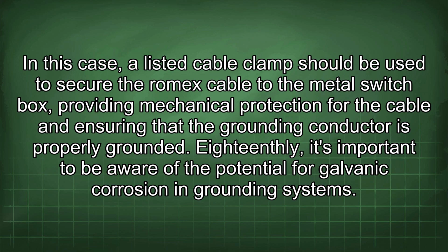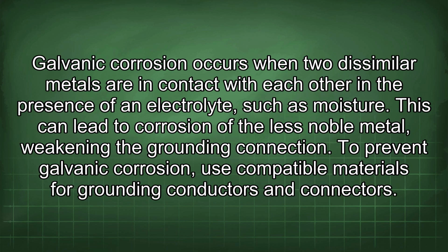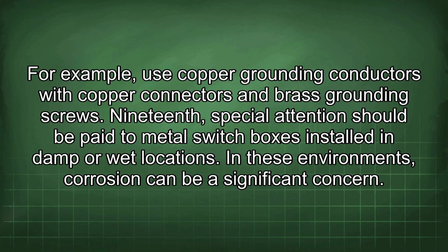18thly, it's important to be aware of the potential for galvanic corrosion in grounding systems. Galvanic corrosion occurs when two dissimilar metals are in contact with each other in the presence of an electrolyte, such as moisture. This can lead to corrosion of the less noble metal, weakening the grounding connection. To prevent galvanic corrosion, use compatible materials for grounding conductors and connectors. For example, use copper grounding conductors with copper connectors and brass grounding screws.